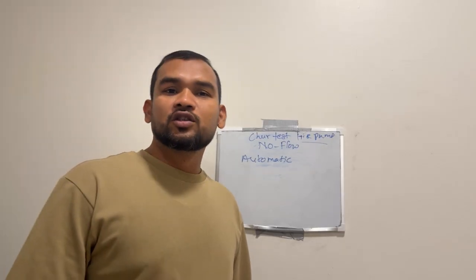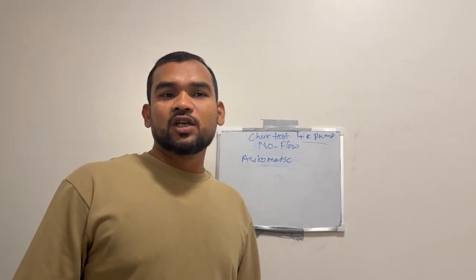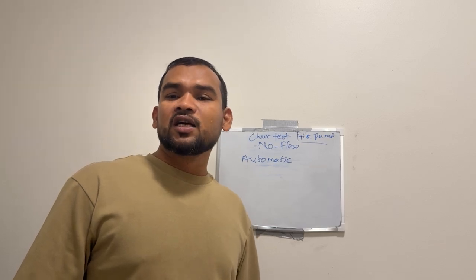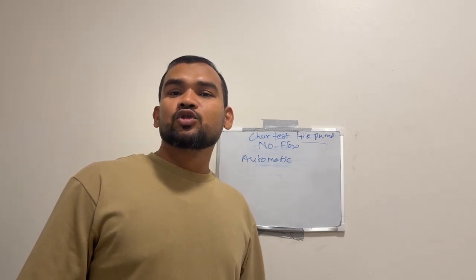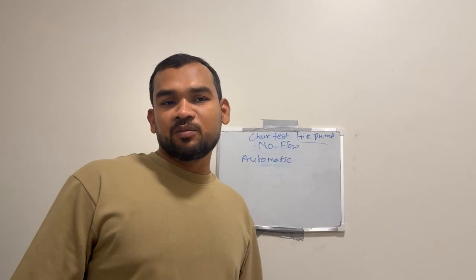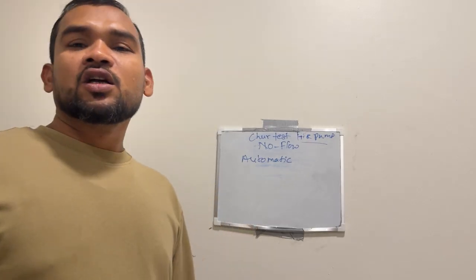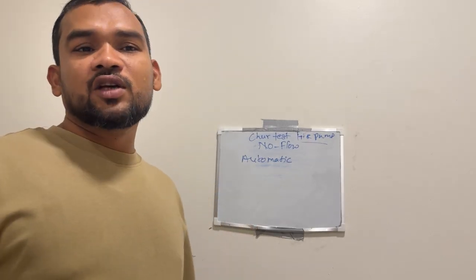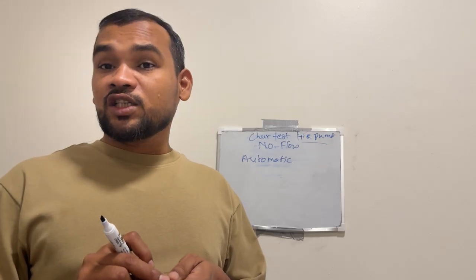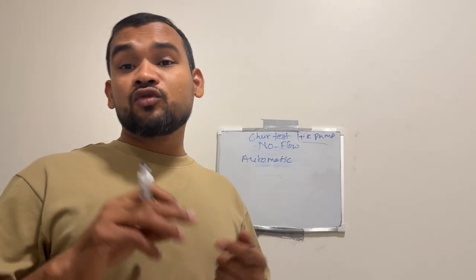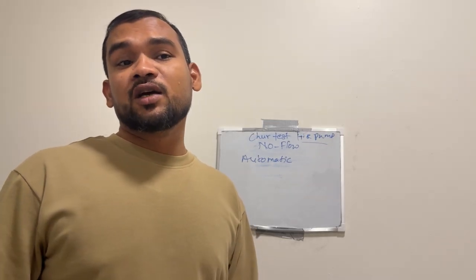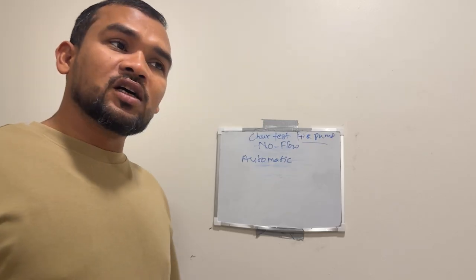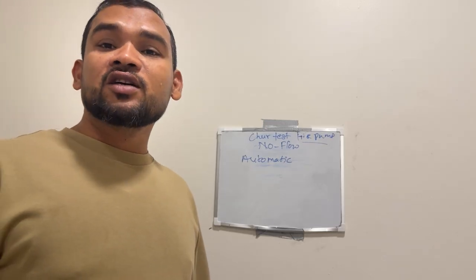And we will check, first, when the electrical pump is running. As per NFPA, the electrical pump should be run for a minimum of 10 minutes, and we have to check the time. We have to check the time of the motor to accelerate to full speed. We have to check the current and voltage reading from the controller.